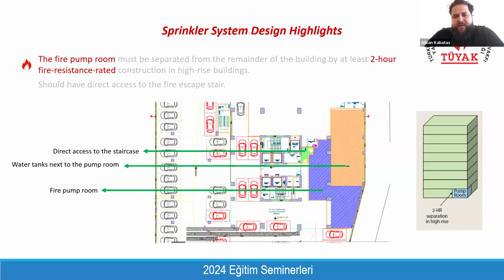But in the basement floor, this fire pump room should be 2-hour fire rated, so that even if you have a fire within the car park, or the neighboring occupancy is just next to the fire pump room, your fire pumps can continue to work in case of fire as well. And during the fire, either the technical team of the building or the fire brigades may need to reach the fire pump room to see whether everything is going right, or to intervene in any failure to start the fire pumps.